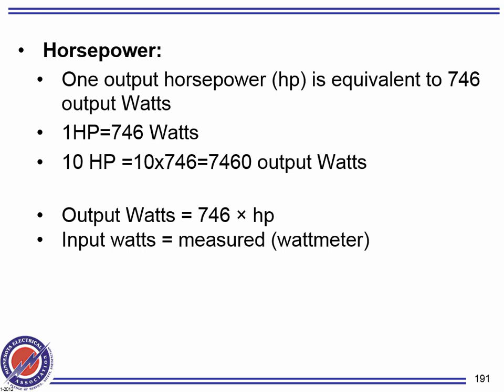Okay, mechanical power to electrical power conversion. How do you convert these? We started with the horsepower in the universe, right? Because we didn't have cars or anything else. So a horsepower is equivalent to 746. So if you need 1 horsepower to run a mechanical machine, efficiency. Remember, every machine has efficiency issues. There's no 100% efficiency. But the conversion factors start right there.